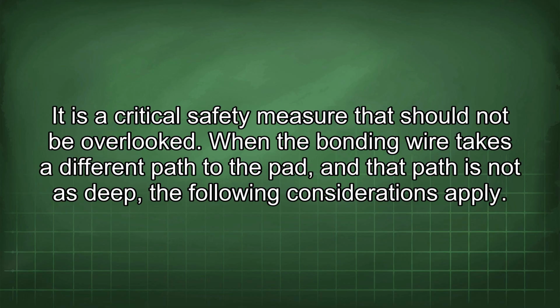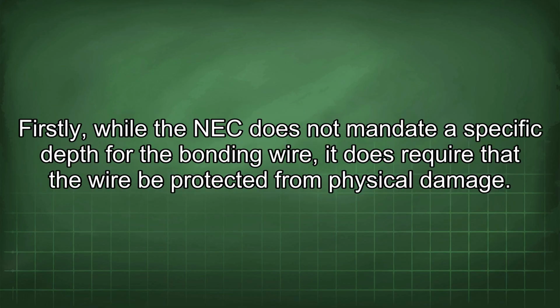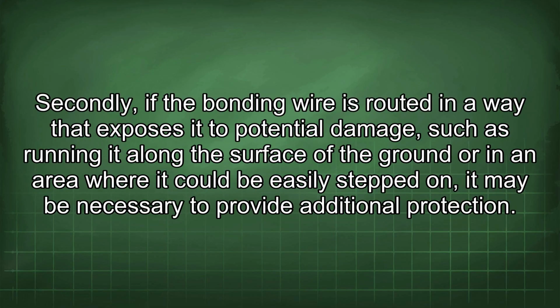When the bonding wire takes a different path to the pad, and that path is not as deep, the following considerations apply. Firstly, while the NEC does not mandate a specific depth for the bonding wire, it does require that the wire be protected from physical damage. Secondly, if the bonding wire is routed in a way that exposes it to potential damage, such as running along the surface of the ground or in an area where it could be easily stepped on, it may be necessary to provide additional protection.